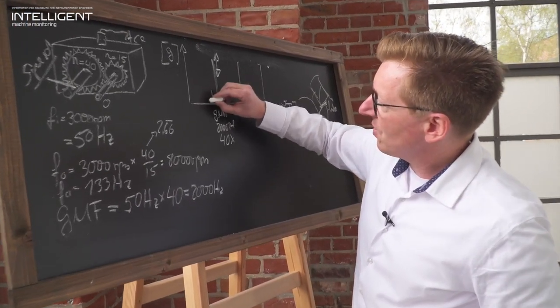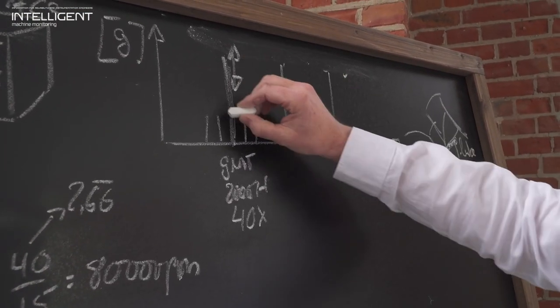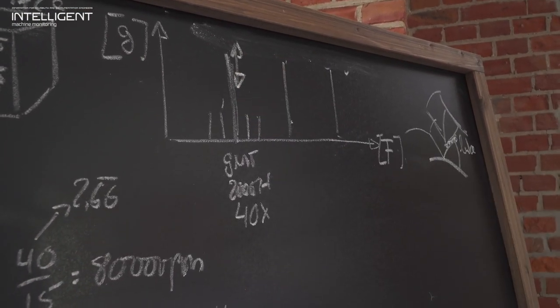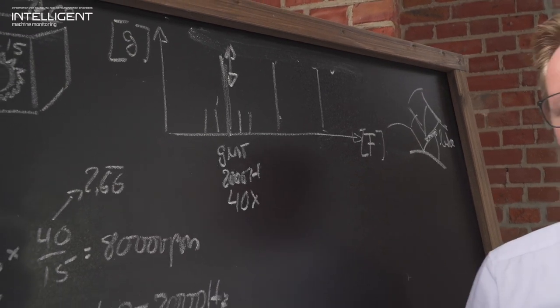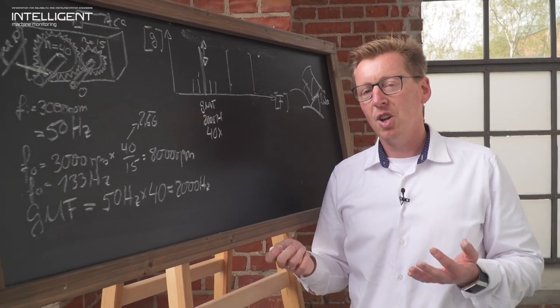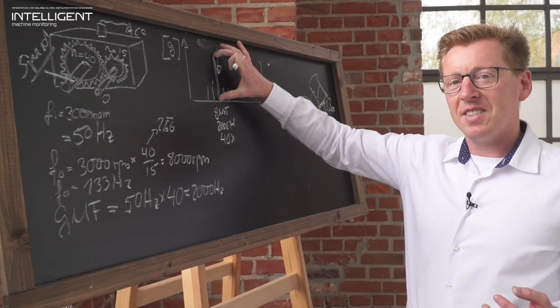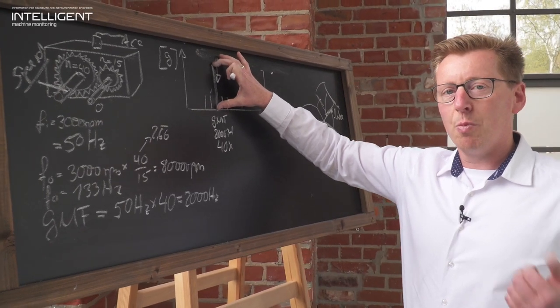You will produce sidebands to the main gear mesh frequency around this main peak, and these are an indication for the quality of the mating or the quality of the contact.